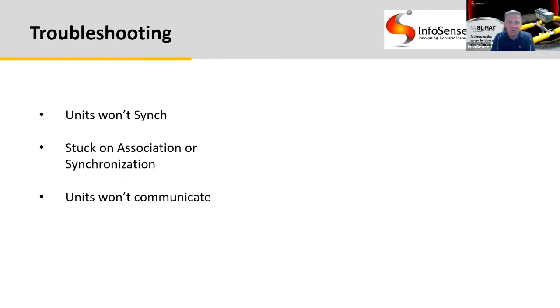If the units won't communicate with each other, they will not upload to a computer and likely won't be able to perform more acoustic tests. They will need to come in for repair of this circuit. One thing to note, if you come across an issue where you cannot upload your measurements from the RX due to a damaged part, we are almost always able to recover that data for you once the units come in for service.